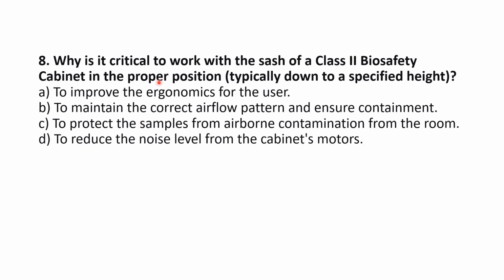Question number 8. Why is it critical to work with the sash of a class 2 biosafety cabinet in the proper position, typically down to a specified height? All right, so A, to improve the ergonomics for the user; B, to maintain the correct airflow pattern and ensure containment; C, to protect the samples from airborne contamination from the room; and D, to reduce the noise level from the cabinet's motor.